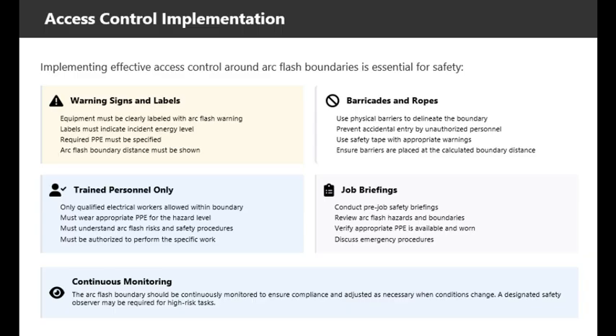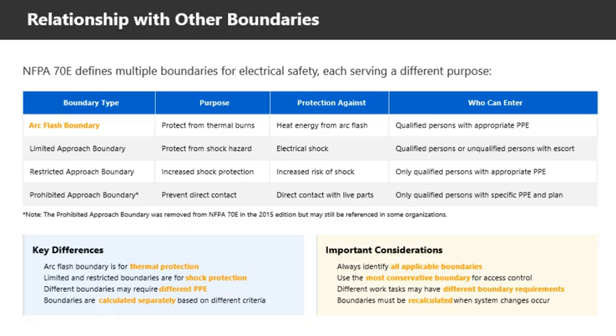Finally, continuous monitoring ensures that the arc flash boundary is respected throughout the work activity. The boundary should be continuously monitored to ensure compliance and adjusted as necessary when conditions change. For high-risk tasks, a designated safety observer may be required to watch for unsafe conditions and ensure procedures are being followed. Remember, access control isn't just about keeping people out, it's about ensuring that those who need to enter are properly protected and prepared. It's important to understand that the arc flash boundary is just one of several boundaries defined by NFPA 70E for electrical safety. Each boundary serves a different purpose and protects against different hazards.